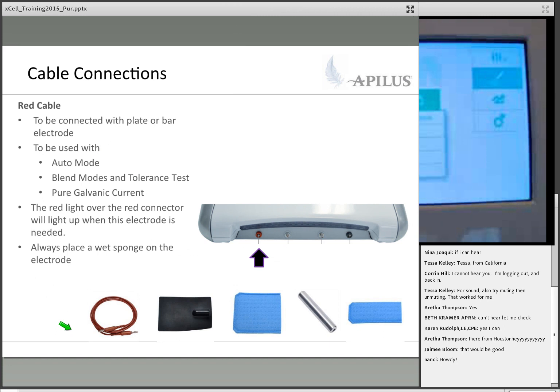On the left side, in the front of the machine, this is where you connect the red cable. The red cable comes with a few different attachments. One is going to be the plate. The plate is the black rubber flat thing. And then you have the bar. The bar is the metal rod here. Both of those will plug into the end of your banana cord here. The other end goes in here. These are the wet sponges that come with a machine. For sanitation purposes, most of the time people will use paper towels that have been wetted or some sort of wipe. All of that is perfectly okay. You want to have some sort of wet connection, wet ground on top of your electrode.